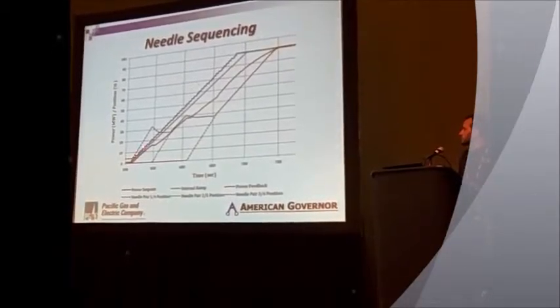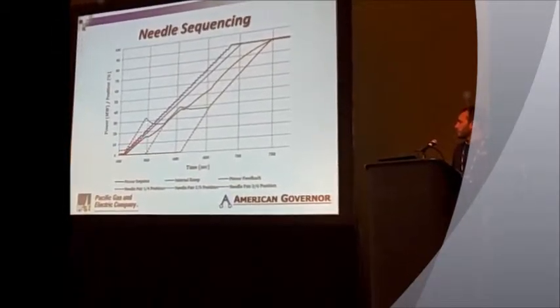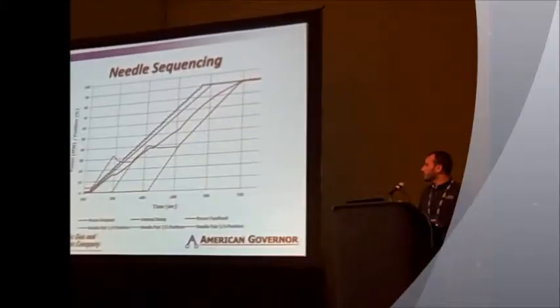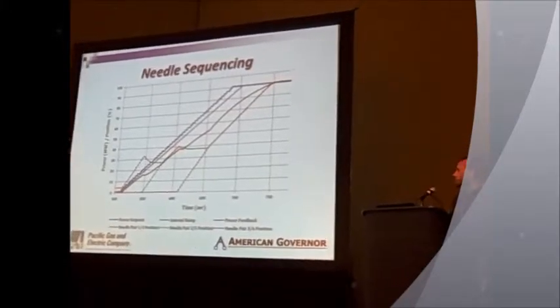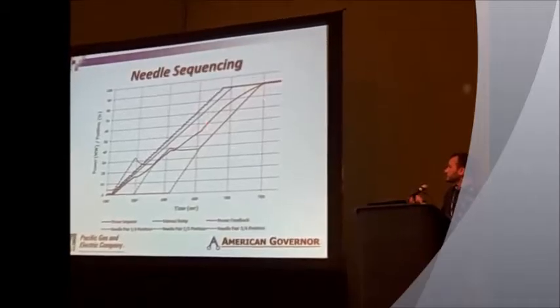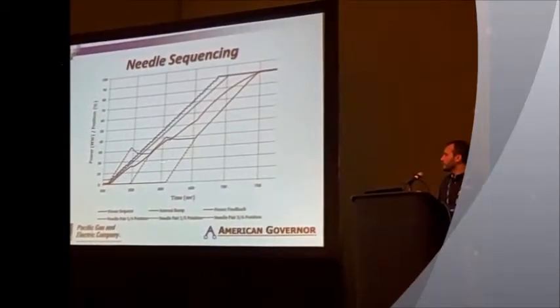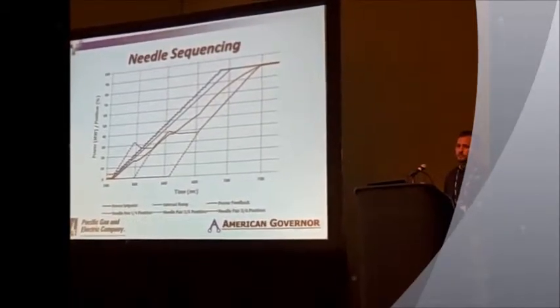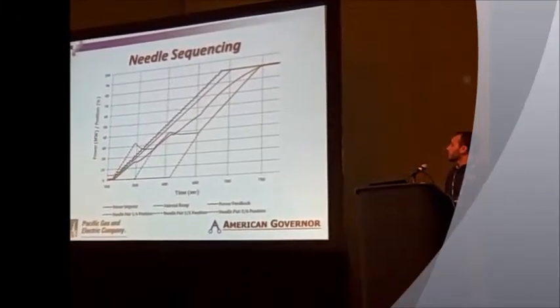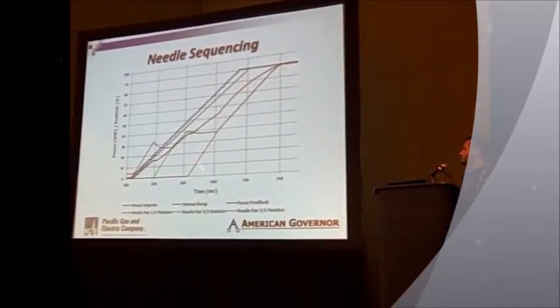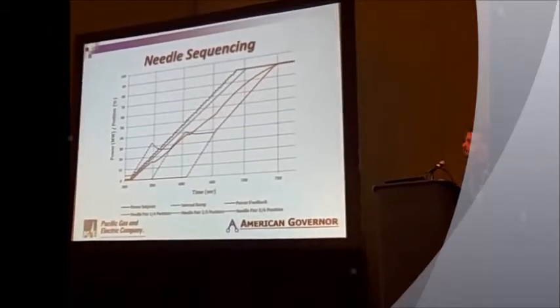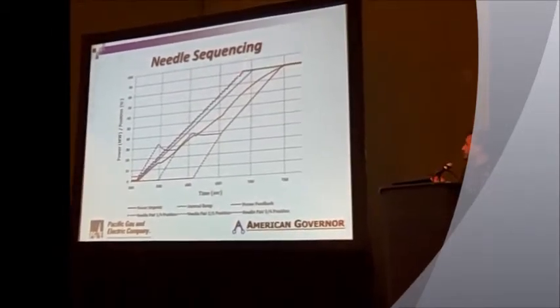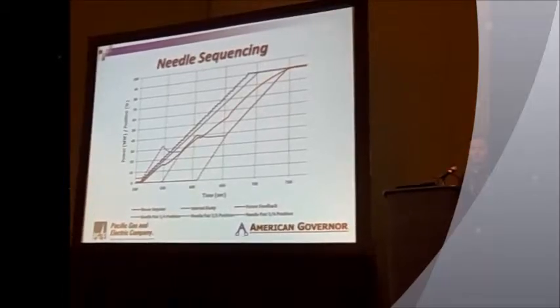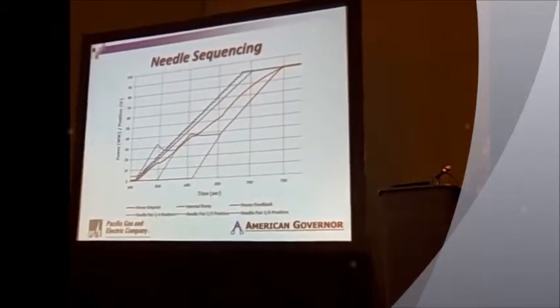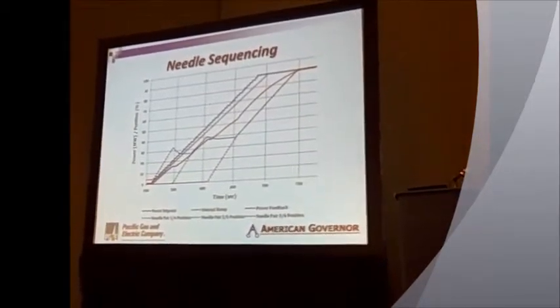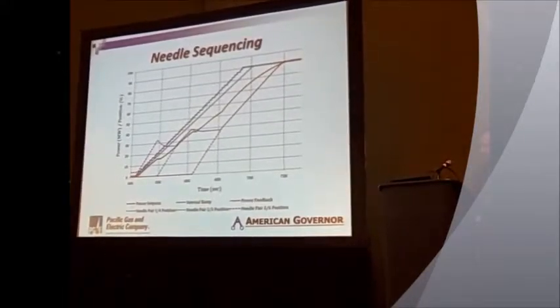What you'll also notice is the rate of change of 1 needle pair moving alone versus the rate of change of 2 needle pairs and 3 needle pairs. The 3 needles are at 1/3 the rate of 1 needle, and 2 needles at half the rate, so that you again get that consistent loading. One other feature that you're not going to see on this chart is if you were running at around 10 megawatts and you put in a set point of 80 or 90, it would immediately transition to 6 needles because it knows that that's where you need to be. And that alleviates some of the long loading concerns they have with the other unit.